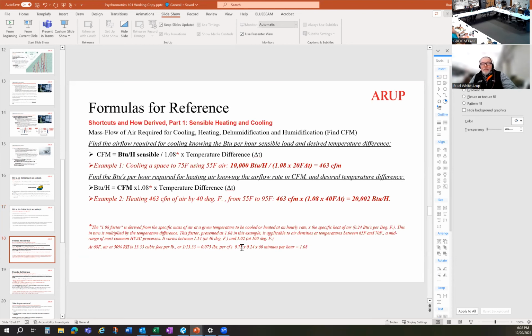Here's the dull part, the formulas. I put these in your handouts in case you ever need them or want to know how they're broken out. Those of you who've done the calculations, by hand or on worksheets, have seen the formulas: 0.68 is a multiplier for humidity for enthalpy, and 1.08 or 1.085 times temperature for CFM, to get your CFM.